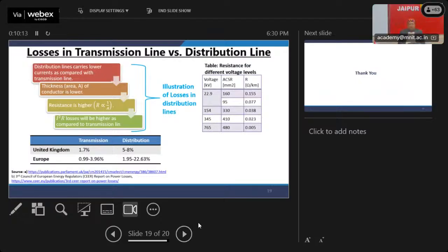So moving to losses in transmission lines versus distribution lines. Distribution lines carry lower current as compared to transmission lines. The cross-sectional area A of the conductor is lower, so resistance is higher, and I square R loss will be higher as compared to transmission lines. So you could see the transmission line losses are close to 1 to 1.7%, and the distribution system is 5 to 8%, let's say. So almost 4 to 5 times higher than transmission loss.